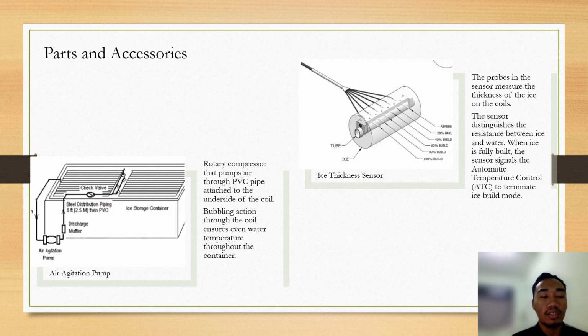Okay, next is the thermal ice storage parts and accessories. The first accessory of the thermal ice storage is the air agitation pump. The pump has a rotary compressor that pumps air through PVC pipe attached to the underside of the coil. The bubbling action through the coil is to ensure even water temperature throughout the container.